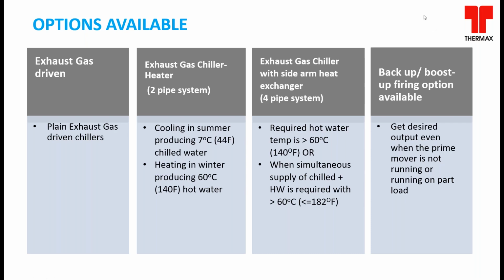The third important possibility is having a backup source. Just as we have a backup in the form of a diesel genset or gas genset for grid power, similarly when recovering heat from exhaust gases there may be scenarios requiring some kind of backup or redundancy, so the system can keep running. This is possible with a natural gas driven backup system built onto the chiller itself, which takes care of scenarios of engine outage.